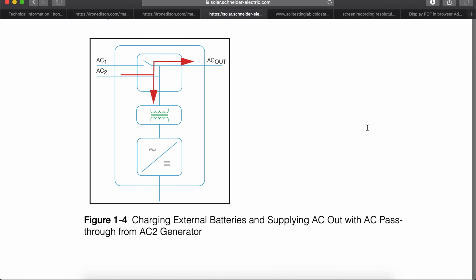In this diagram, figure 1-4, we're charging batteries and supplying AC output with pass-through from AC2 generator. So in this scenario, you can see the connection to the grid has disconnected. We're now connected to a running generator coming in on AC2. In this scenario, much like the last, we're converting some of that energy for battery charging. Down here would be the battery. Here would be the transformer for charging that battery. And then here's the AC output.